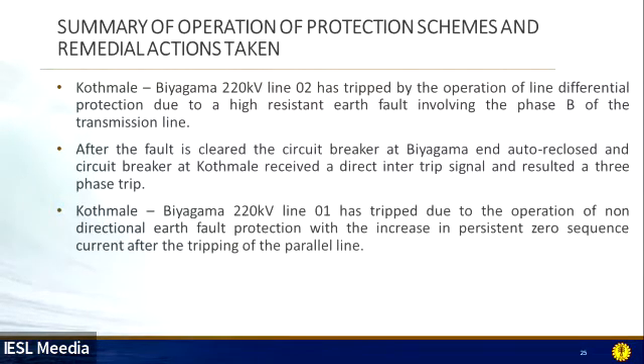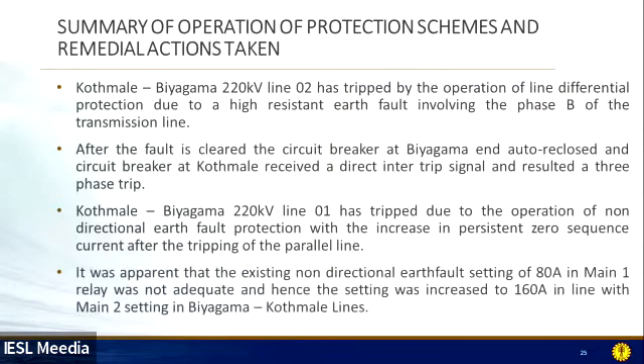Kothmale Biyagama 220kV line 1 tripped due to the operation of non-directional earth fault protection, with the increase in persistent zero sequence current after tripping of the parallel line. It was apparent that the existing non-directional earth fault setting of 80 ampere in the main 1 relay was not adequate, and hence the setting was increased to 160 ampere, in line with the main 2 setting of the Biyagama Kothmale line. That is one activity carried out by the control and protection staff so that this backup protection relay operation of the Kothmale Biyagama lines does not reoccur.